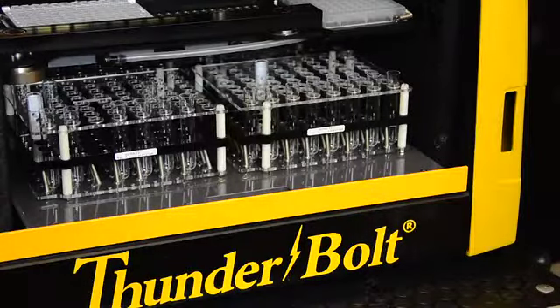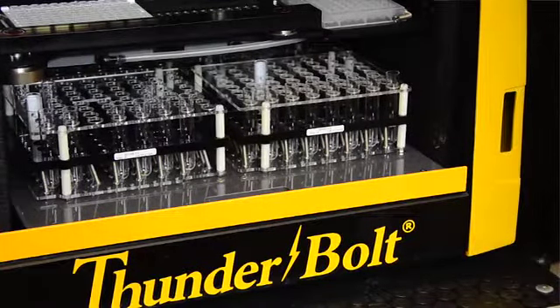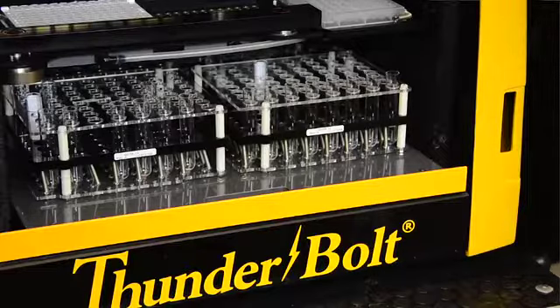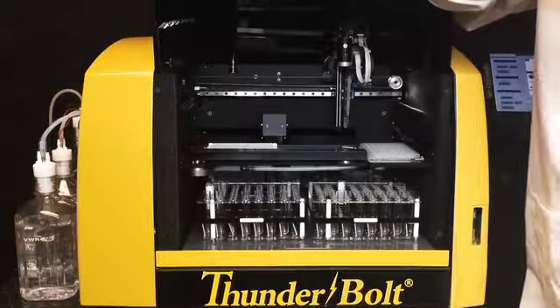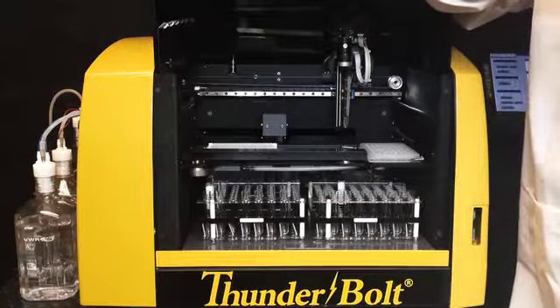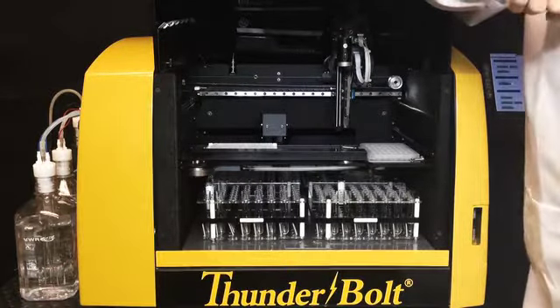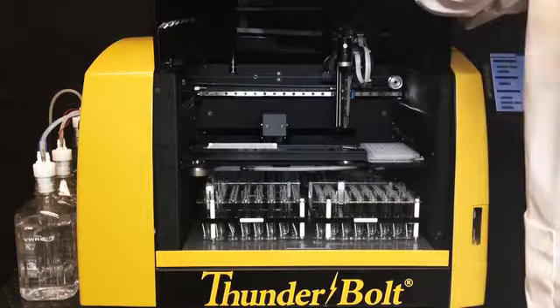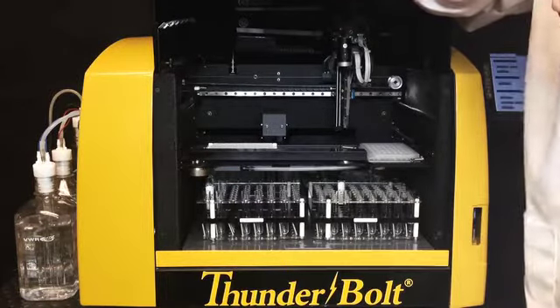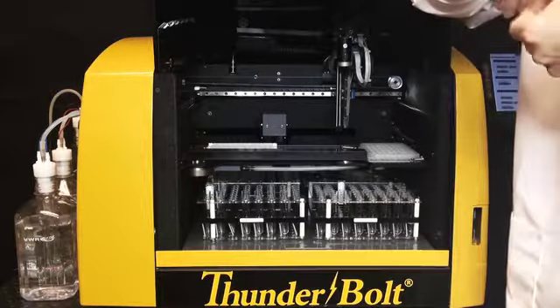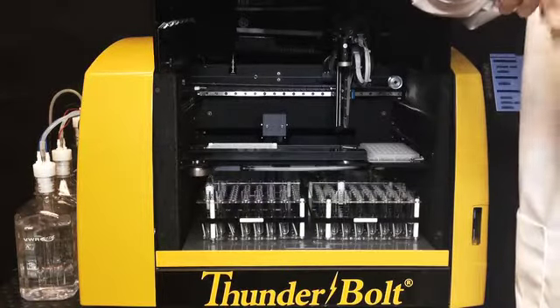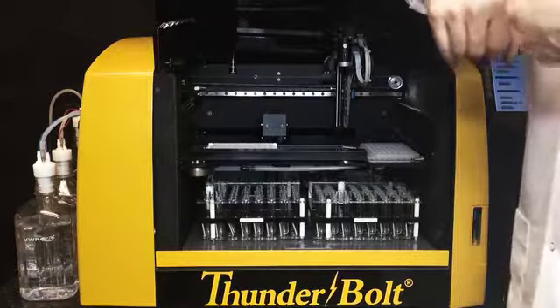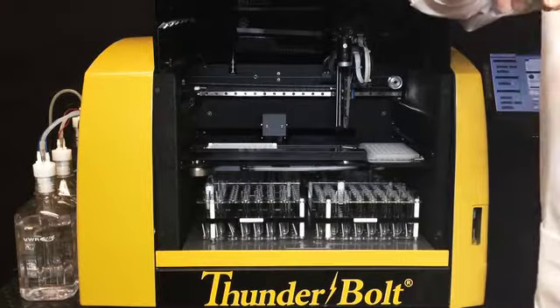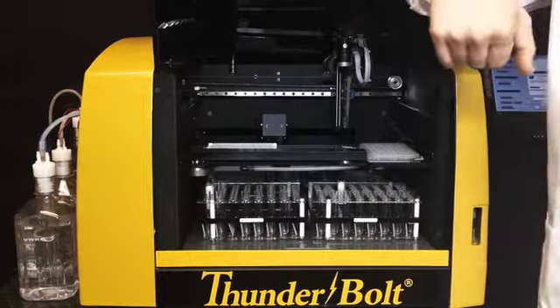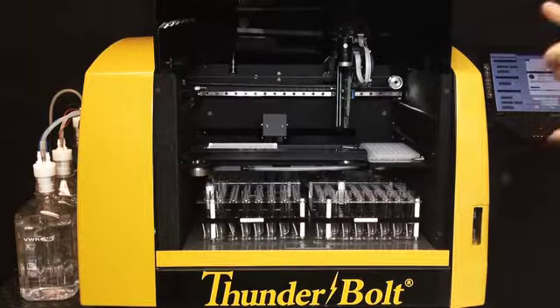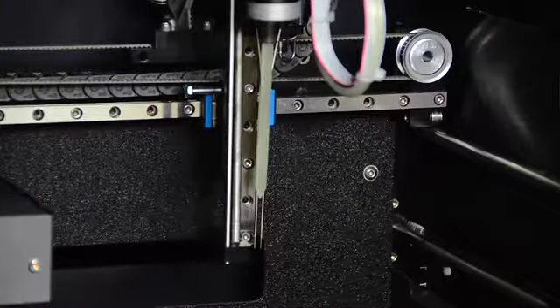The last thing that I wanted to mention once again is the emphasis of the 1 to 100 dilution. Many infectious disease products and other kits have dilutions that require pipetting of small volumes. That may be 1 microliter, 2 microliter, 5 microliters, 10 microliters. Most instruments cannot pick up and deliver anything lower than 10 microliters. We can't do that directly, but what we do is we make the dilution for them. So we pick up 100 microliters of diluent and 1 microliter of sample, doing a 1 to 101 dilution, and then we deliver that directly into the well.